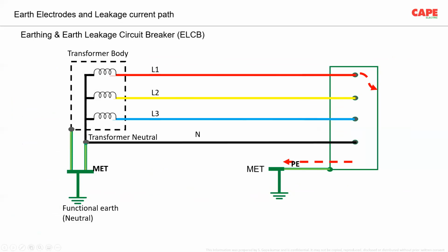So, yeah, sometimes troubles. Now, the fault loop. Imagine on the left side, I'm showing a transformer, a 3-phase connection. There is an equipment or probably an installation. There is a leakage current in the installation. The current goes through the earth electrode to the soil, and it returns back to the source through the earth electrode at the neutral of the transformer. This is called a TT system.